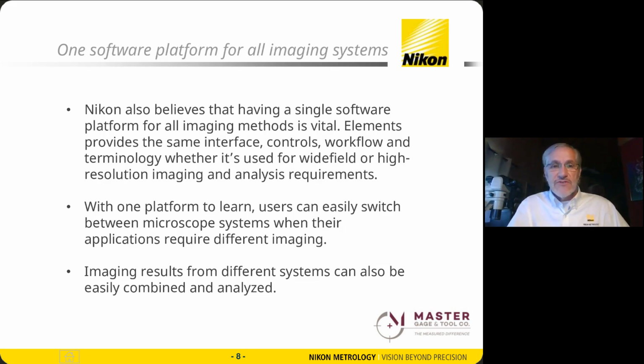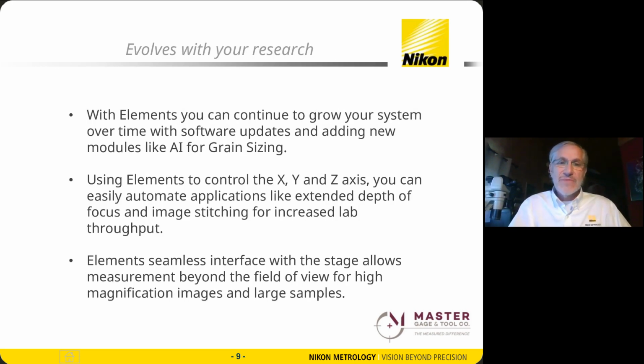We can even bring in images from other platforms. As long as they have a measurement bar, we can bring it into Nikon Elements. We can use a measurement bar to calibrate our system and then perform analysis on those images. Elements continues to grow as your requirements grow and as the industry changes. A good example is grain sizing. Grain size is a difficult thresholding technique which requires very good sample preparation, which is not always the case in the real world. That's the reason we developed AI to support grain sizing, to make it much easier to come up with an ASTM standard number.